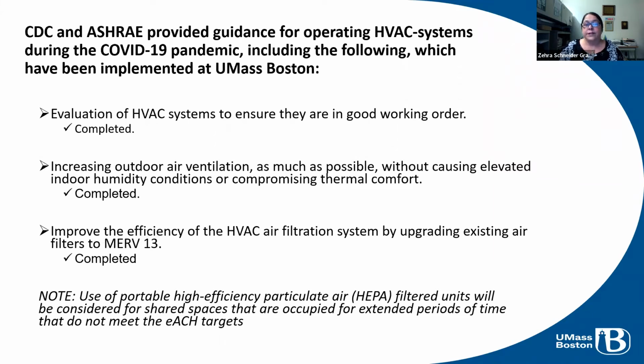Upgrades to the system have included putting in MERV 13 filters, which was also a recommendation. We've also increased the outdoor air ventilation as much as possible, balancing how much we can bring in, particularly during summer months where we don't want to increase humidity, or winter months where we don't want to compromise thermal comfort. Also, the use of portable air filters is recommended in shared spaces occupied for extended times that don't meet the targets set by these governing bodies.